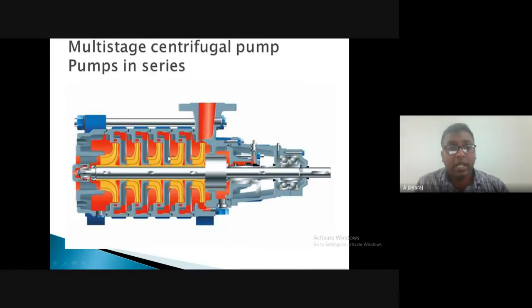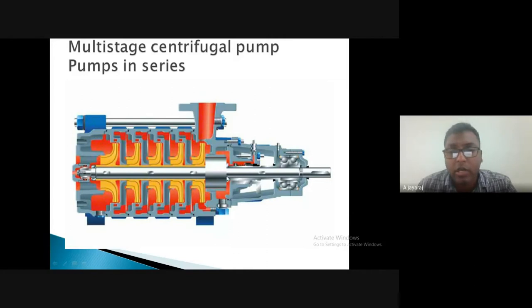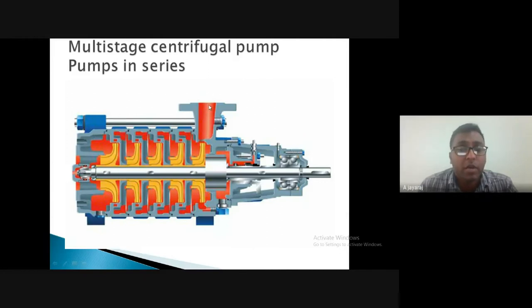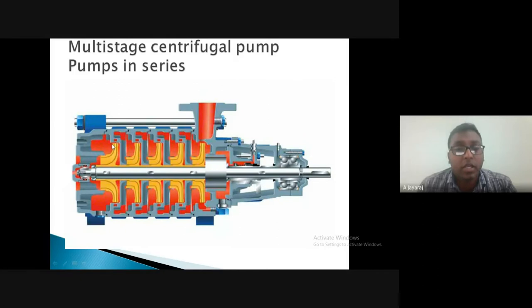In the diagram of pumps connected in series, multiple impellers are connected to a common shaft with one suction line and one delivery line. The outlet manifold of one impeller becomes the inlet for the next pump, through successive stages, finally producing one output at much higher pressure. The water pressure is increased to a very high level through multiple stages.